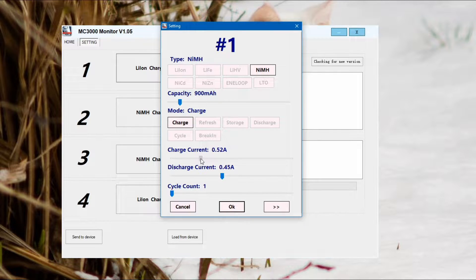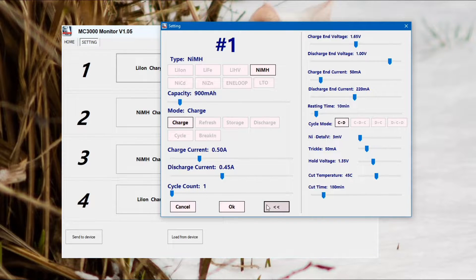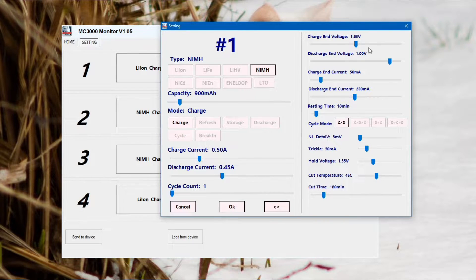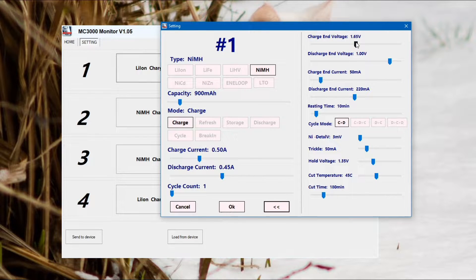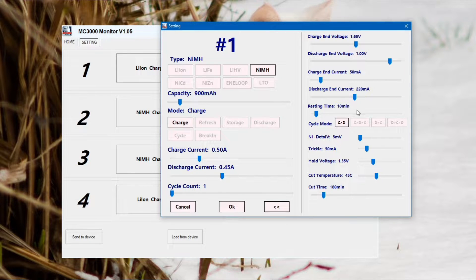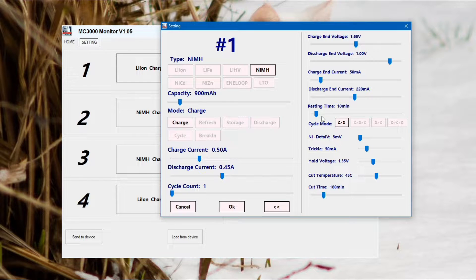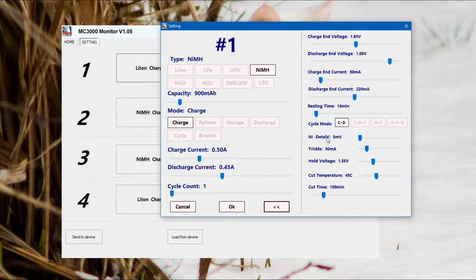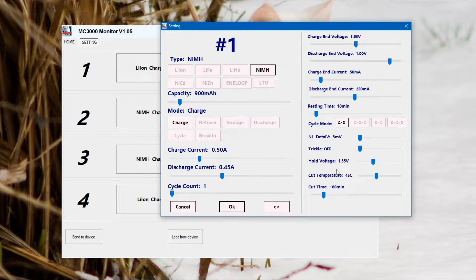If you click that right hand button with the arrows on it, you'll get the more advanced controls. This allows you to change things like the termination, the end voltage, and the end current as well. The cycle modes are pretty much self-explanatory. C is charge, D is discharge, so you can run multiple cycles and I'll show you an example later on, just doing a discharge capacity test.